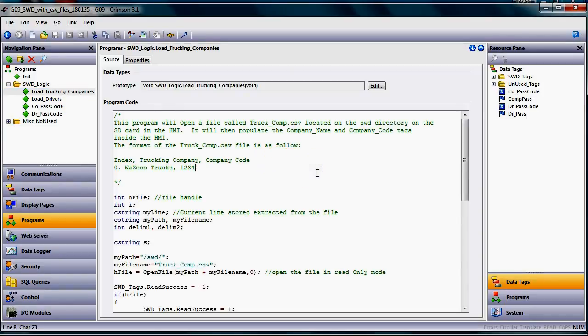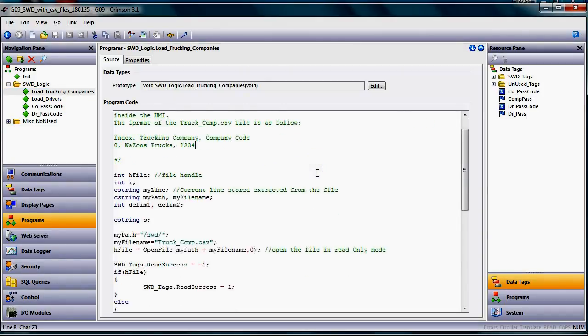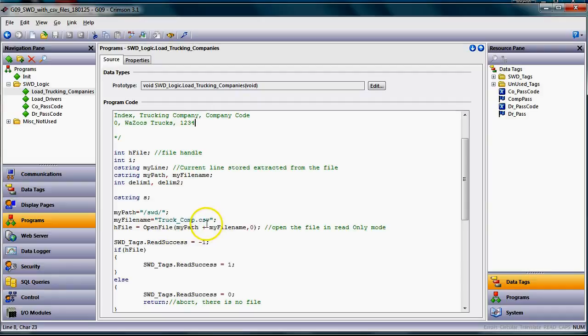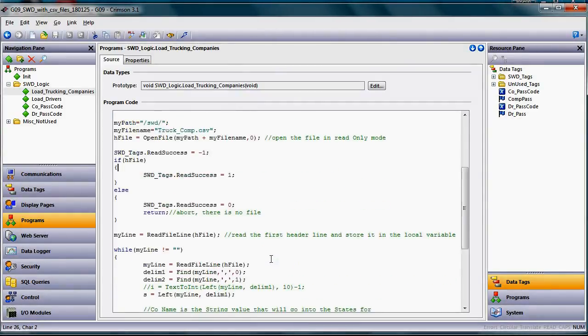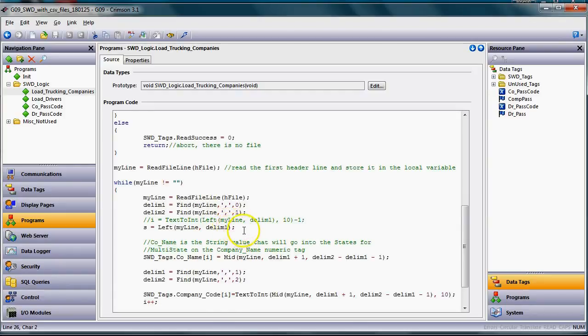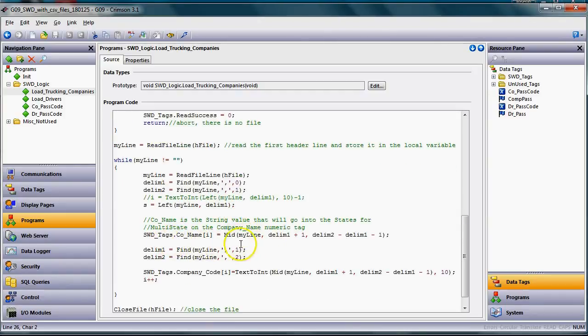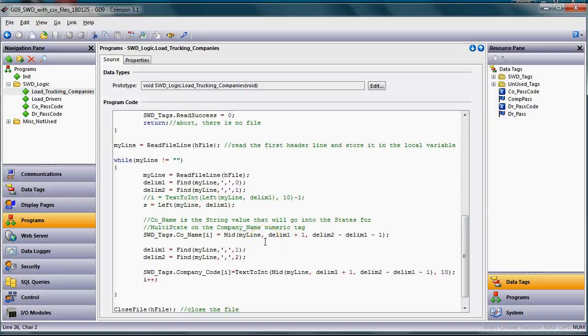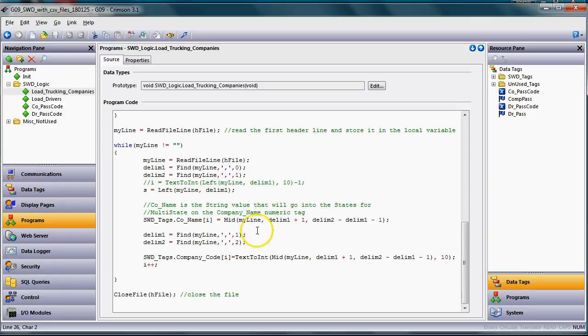So if you look here, there's the saltwater disposal site path for the directory and there's the name of the file that's on there. You could of course make this a tag and navigate manually if you want to. But nonetheless, what I have is a simple while loop that reads each line and if there's a blank line it's done to the end of the file. But if not it actually takes the tag name and puts the company name into a certain field in here and I'm using a function called mid which will go in and find the commas and then does some logic based on the location of the commas and how many characters that you want, left or right of the comma. So that's what happens there, it loads in those values.